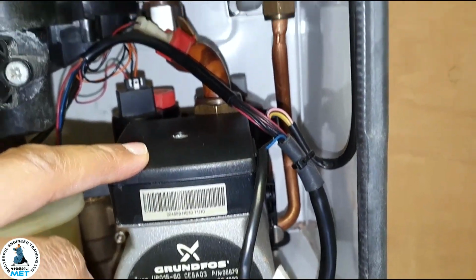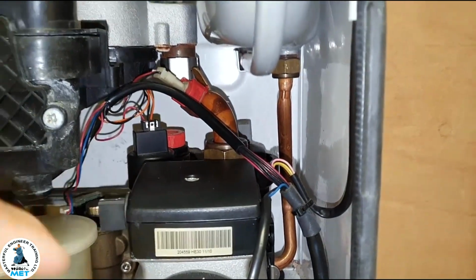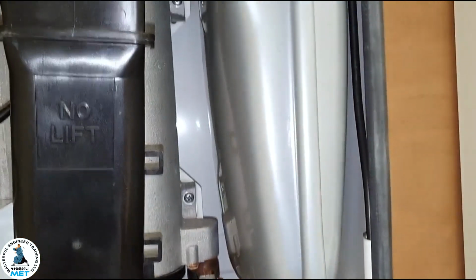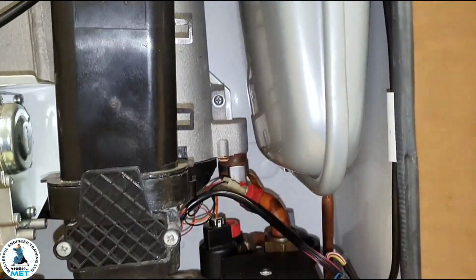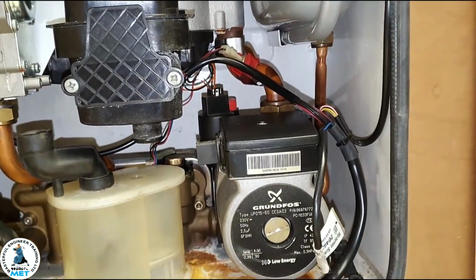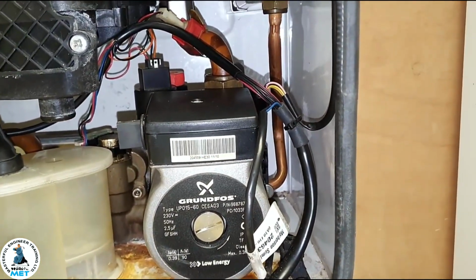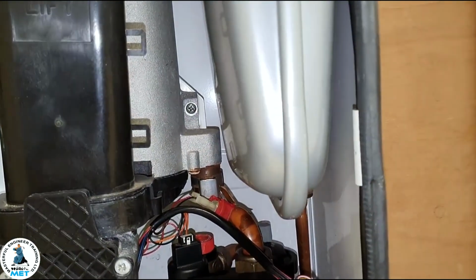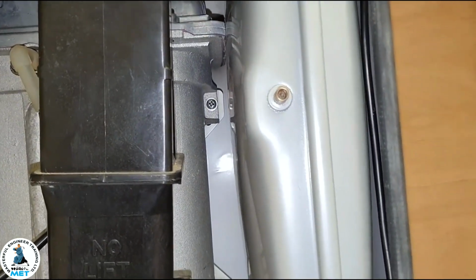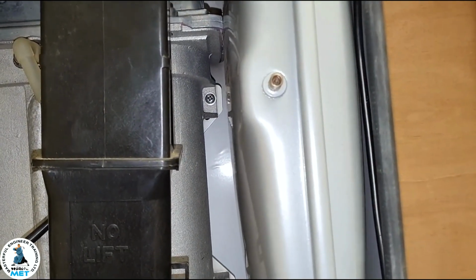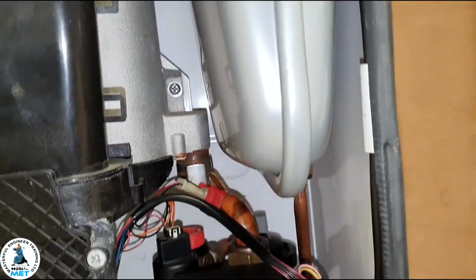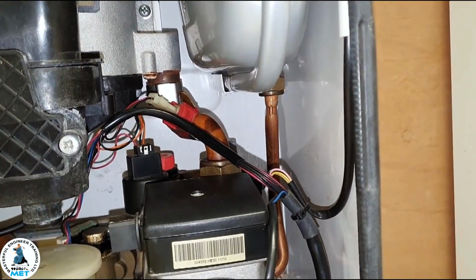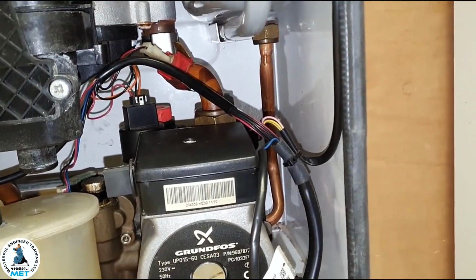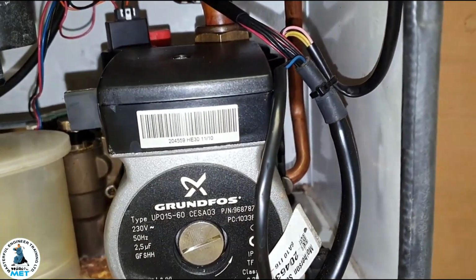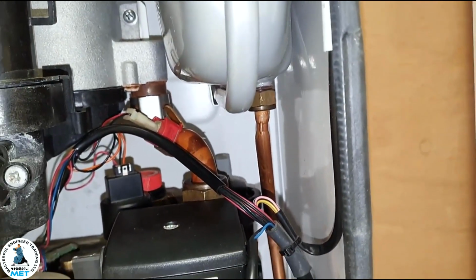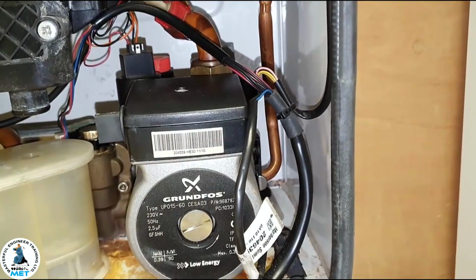Actually, you said something quite good, going back to the pressure loss issue. The other thing it could be, we might check the expansion vessel and find it's actually fine, there's air in it, but we could have a blocked pipe, which can give the same problem, over-expanding because the pipe is blocked.